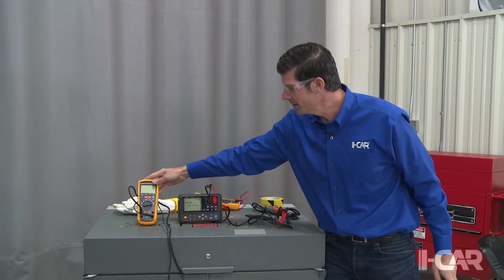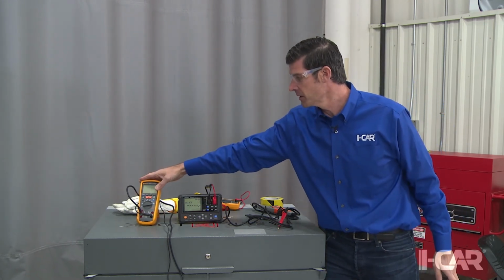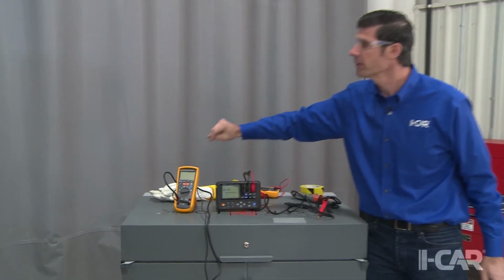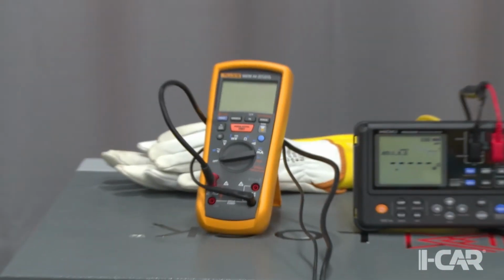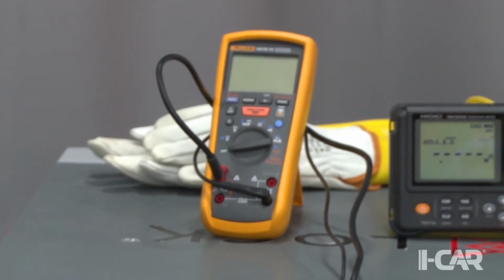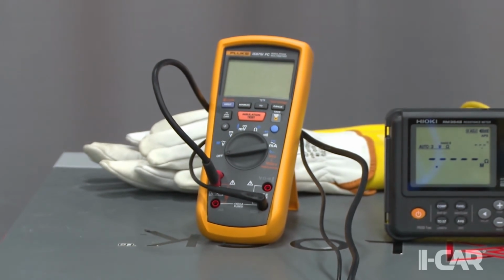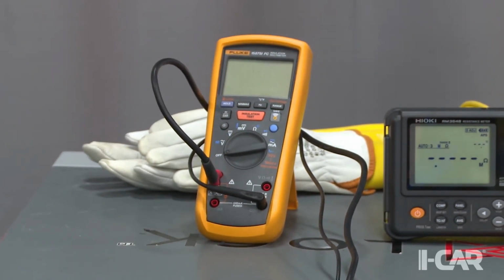This insulation tester, you can select between 500 and 1000 volts. In this case, I would select 500 volts and apply high voltage plus against ground, high voltage minus against ground, to verify if there's any insulation error between my high voltage plus connector and ground.